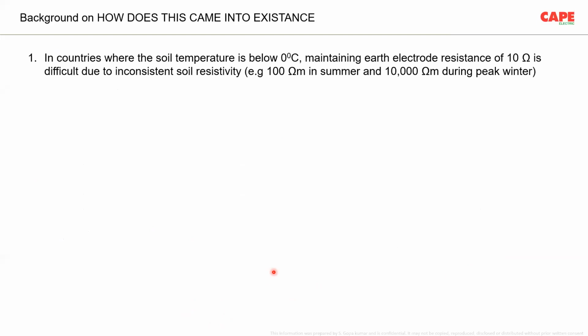In countries where the soil temperature is below 0 degrees centigrade, imagine Russia or America, maintaining an earth electrode resistance of 10 ohm is difficult. Where is this 10 ohm required? 10 ohm is required for a type A earth electrode for a lightning protection system. Maintaining it is difficult due to the inconsistent soil resistivity.